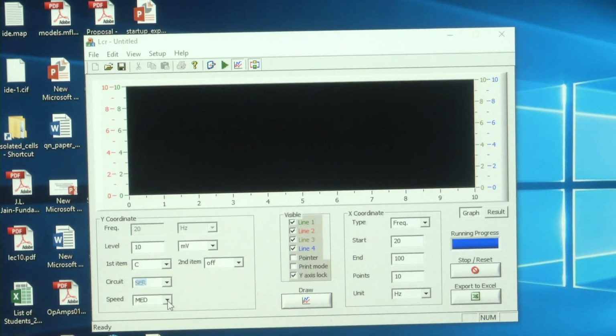Then, what is the speed with which you want to do the sweep? This software will be doing a sweep across the frequencies. If you give a low speed, it will give a much more accurate value. If you give a fast sweep, the sweep will happen very fast, but the accuracy will come down. So, anything in life comes with a cost. If you want fast measurement, your accuracy will go down. Let us keep it medium. It is neither slow nor fast.